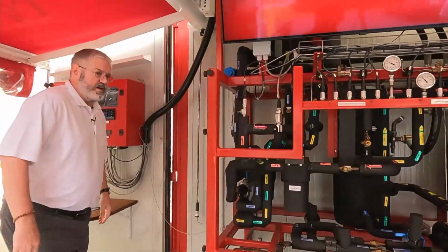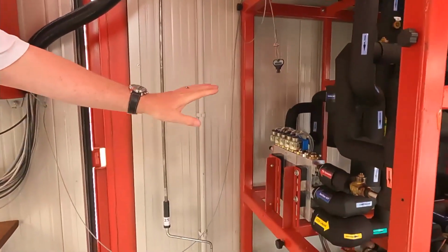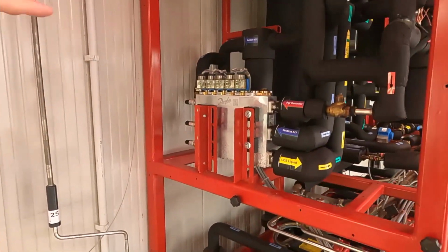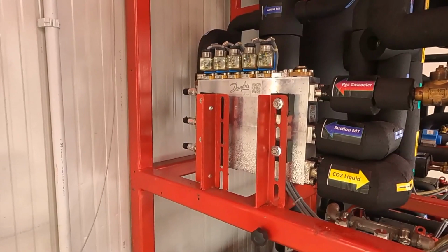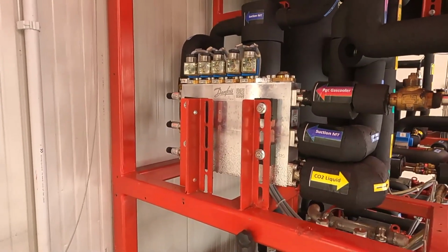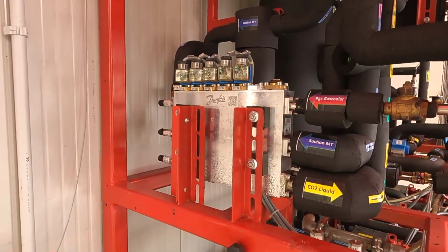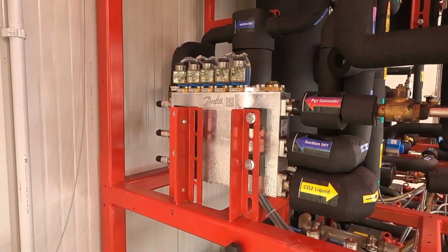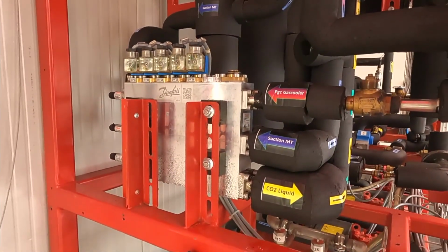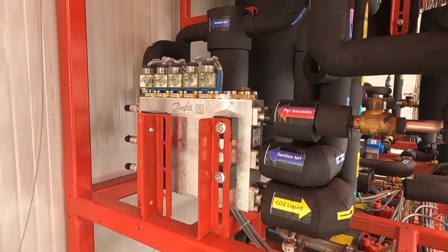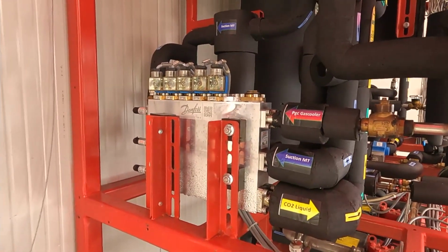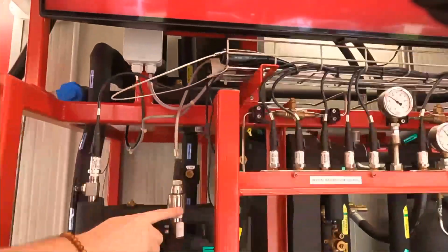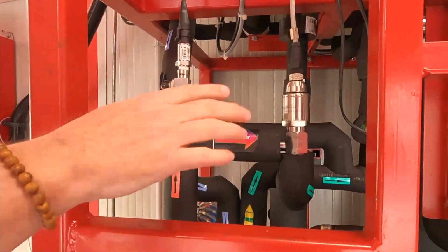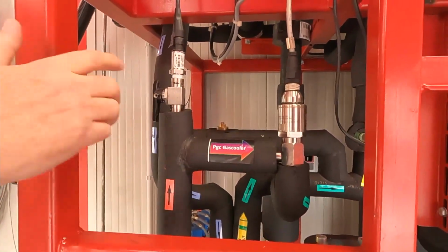So the ejector block on our system, it's over on the left side of the unit. This system was likely retrofitted with it, and that was the best place for it. But this is our ejector block here, and it is between the gas cooler and the entry into the flash tank. And then in parallel with this is our high pressure valve up here. We come around the front here. This is our high pressure valve. One thing I'll note, I mentioned earlier that you don't have to have both of them.